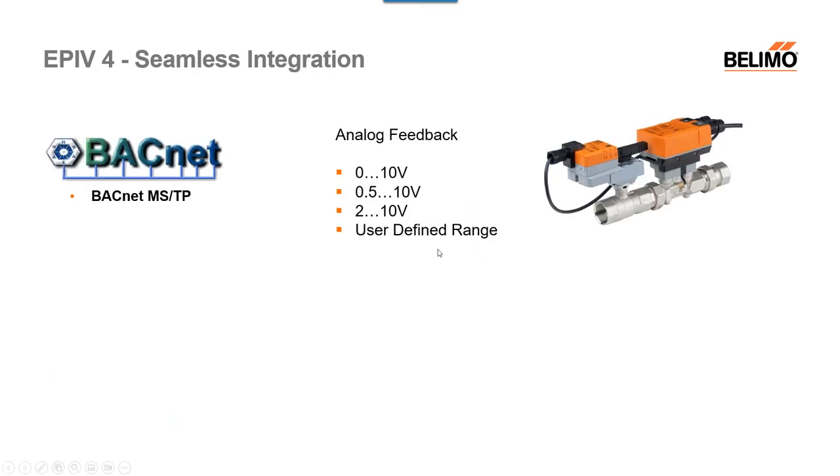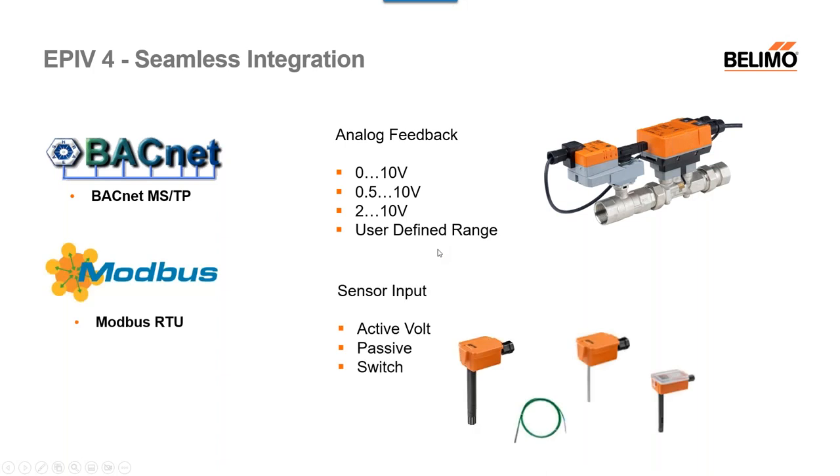As I mentioned before, BACnet and Modbus are both available for the EPIV 4s across the entire line. It still has analog feedback options: 0 to 10 volt, 0.5 to 10 volt, 2 to 10 volt, and even a user-defined range. In the Belimo System app, if you need a 2 to 9 volt system for example, you can configure that. After making any changes, you'll see a 'write' button — click it and it downloads to your valve. With the EPIV 4s, there is now the ability to have a sensor input, which was not available previously.